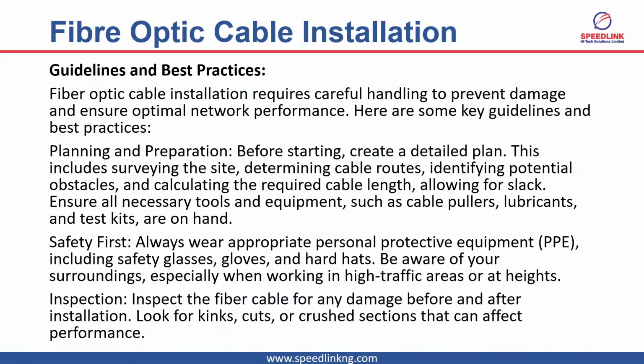Now, since you're passing this cable underground, you don't know exactly what has been passed underground, isn't it? Before you came to work, some other persons must have done their own cable and passed it underground. So before you engage in such activities, you have to first cross-check the area and know the levels of each underground tunnel around that area, so that when you're making your own pit to cross-bore your cable, you can decrease or increase your level where you are digging, so that you're not going to break another person's pipe or cable, isn't it?